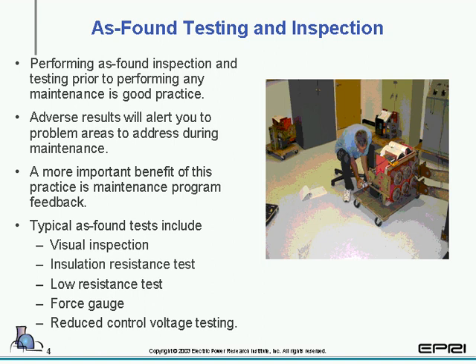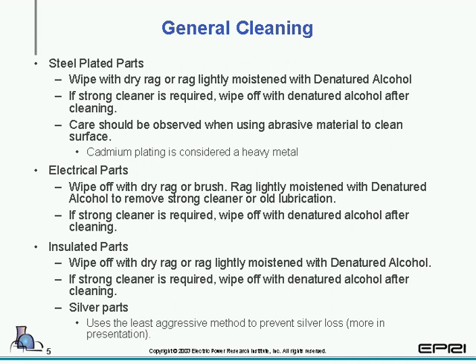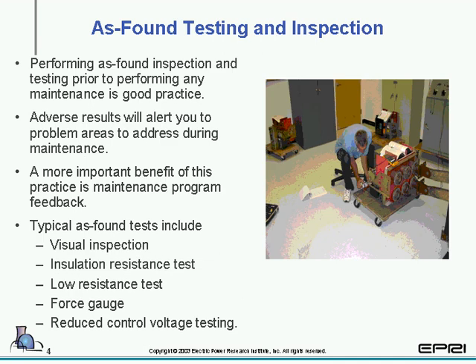And visual inspection is standard. Insulation resistance, low resistance testing or ductoring, and then force gauge and reduced control voltage. These last two are very good indicators of the shape that the equipment is in as far as functioning. Force gauge will tell you if things are binding, and reduced control voltage will tell you the overall condition of the electrical, but no single test is a true indicator of the shape of the equipment.